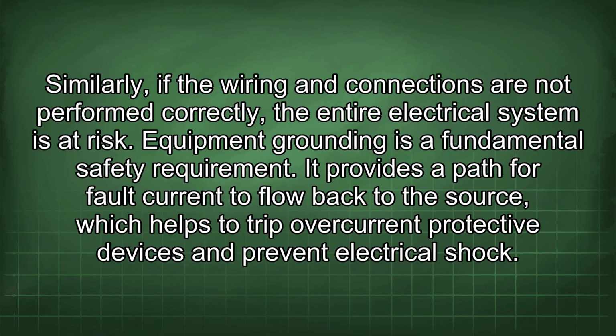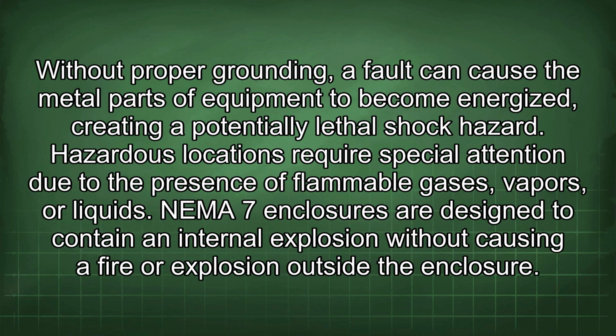Equipment grounding is a fundamental safety requirement. It provides a path for fault current to flow back to the source, which helps to trip overcurrent protective devices and prevent electrical shock. Without proper grounding, a fault can cause the metal parts of equipment to become energized, creating a potentially lethal shock hazard. Hazardous locations require special attention due to the presence of flammable gases, vapors, or liquids.